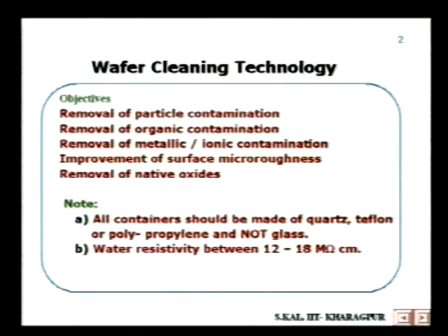Water resistivity should be between 12 to 18 megohm centimeter, and this water is known as deionized water. Normal water which we drink every day or use in our household has a much lower resistivity, because normal water contains a lot of metallic ions and minerals.